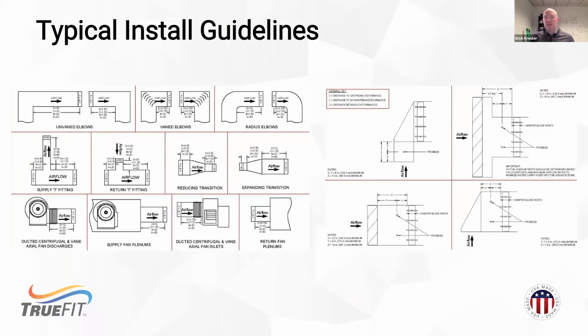So looking at a few typical issues we have, putting airflow measurement where we need to. One thing that we see a lot of times is, equipment today is getting smaller and smaller, and the ductwork installed generally can be limiting as to where you can put proper airflow measurement. Typical install guidelines want laminar flow. That means so many duct diameters away from bends or elbows, vanes, transitions increasing or decreasing. So there's a lot of restrictions that we would typically have to manage. In rooftops, especially, or unit ventilators, you wouldn't have any ductwork necessarily to provide that proper laminar flow, which again is an issue for existing technologies. And I think when we get into technology of how TrueFit works, you'll see why that's not an impact for our method of measurement.